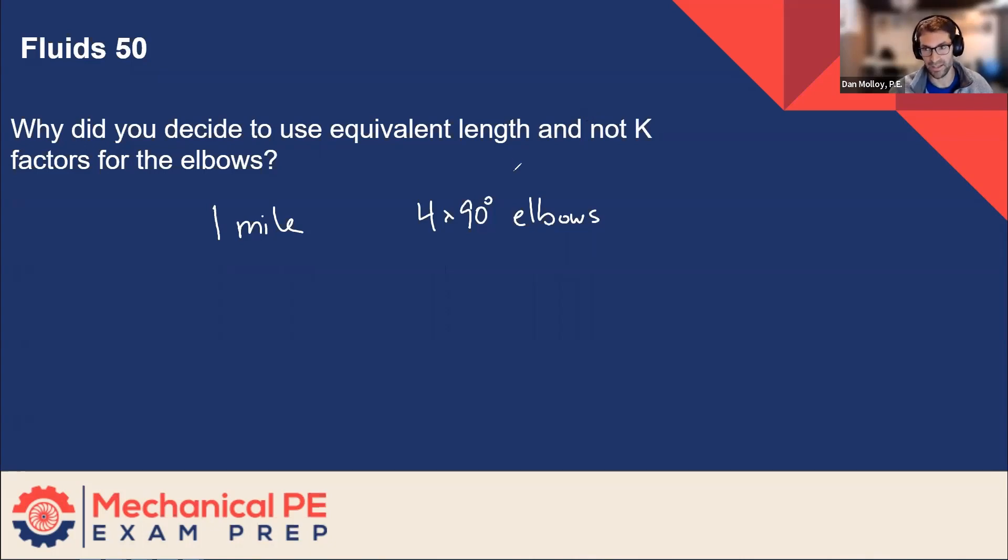So my answer to that is you can use the K factors and it should come out to be approximately the same. The equivalent length is kind of the old method from the paper and pencil days but it's still viable in these computer-based days.